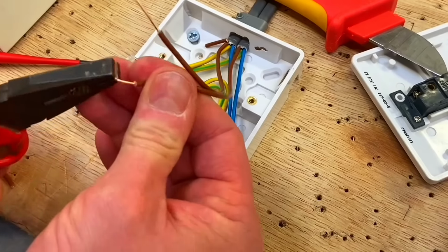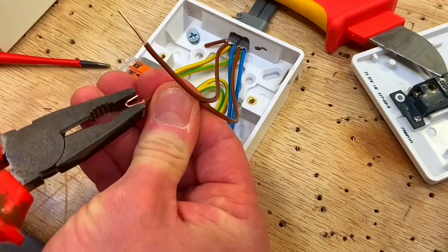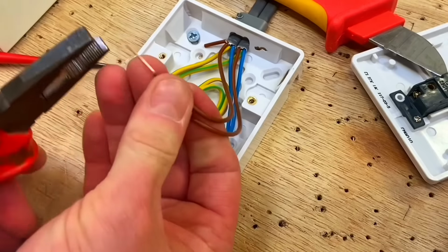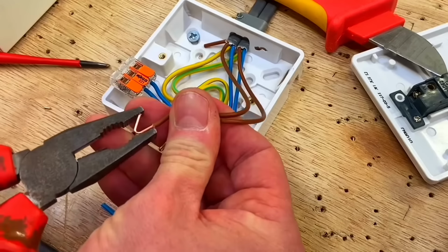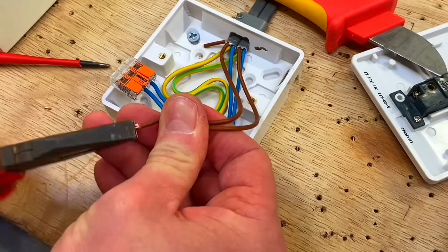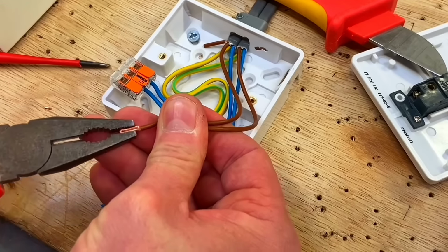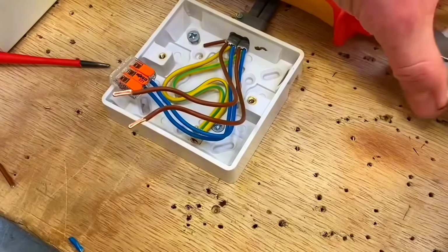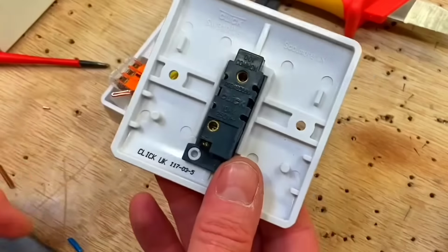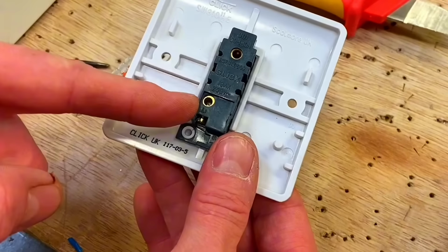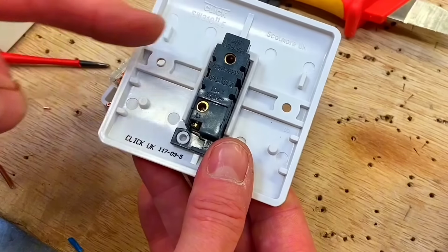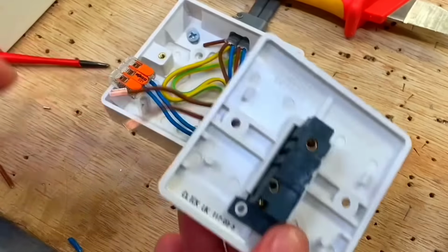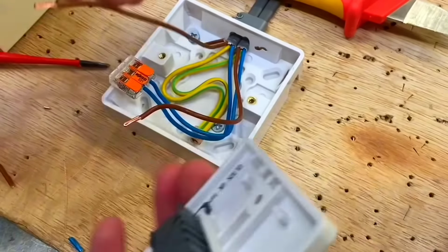Taking slightly less than half, folding it against itself, squeezing up the gap, taking slightly less than half, folding it over, squeezing it up against itself, get rid of that gap. So I've got 2 doubled over terminations. The switch I'm going to use is a one-way switch, common and L1. Doesn't really matter which way around they go, but I will put the incoming line conductor in common and the switching line in L1.